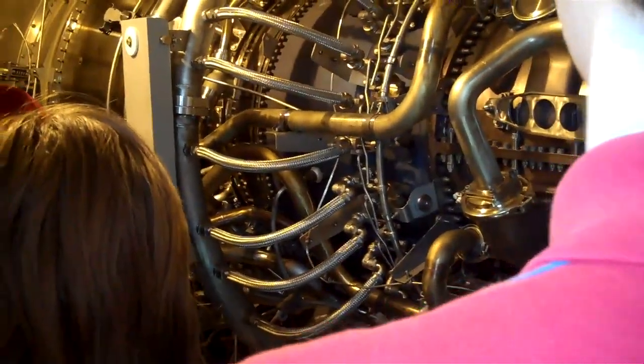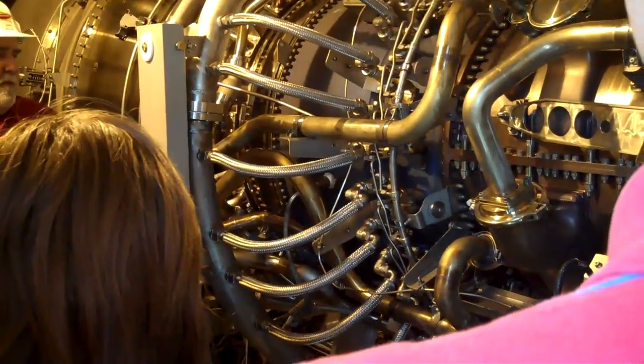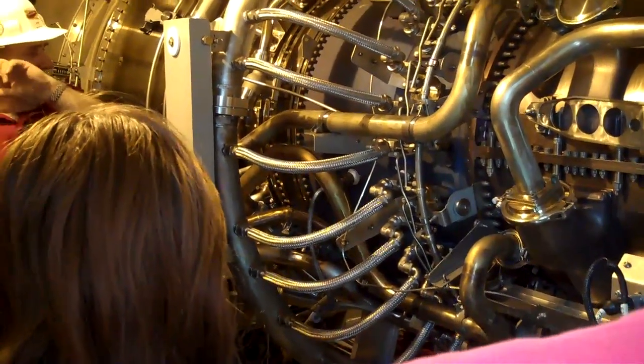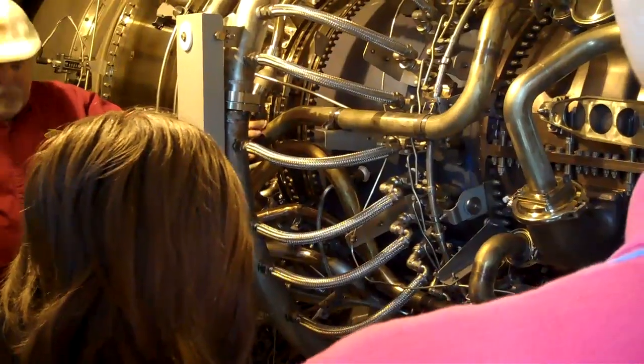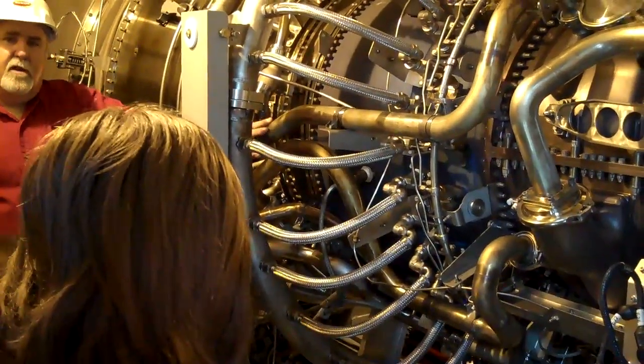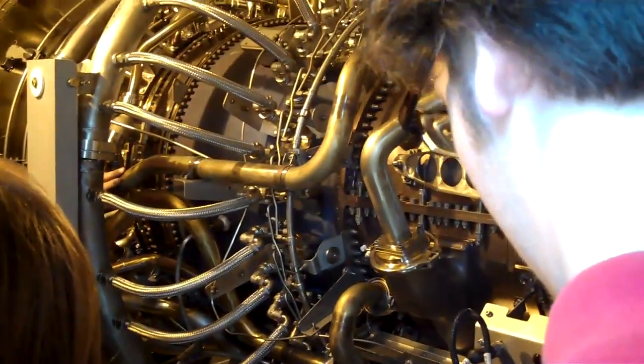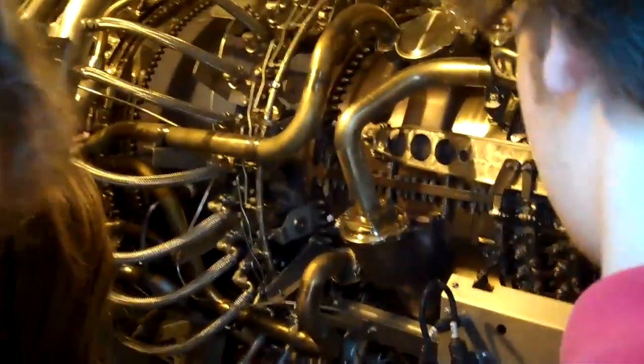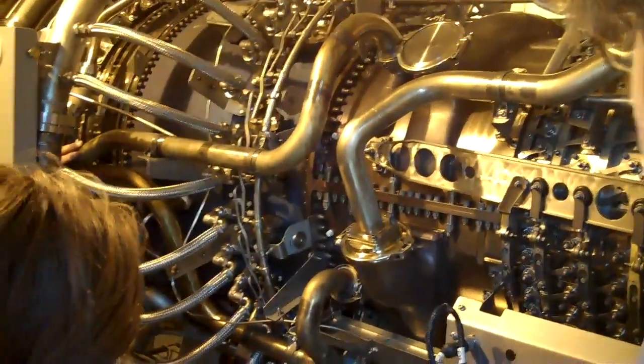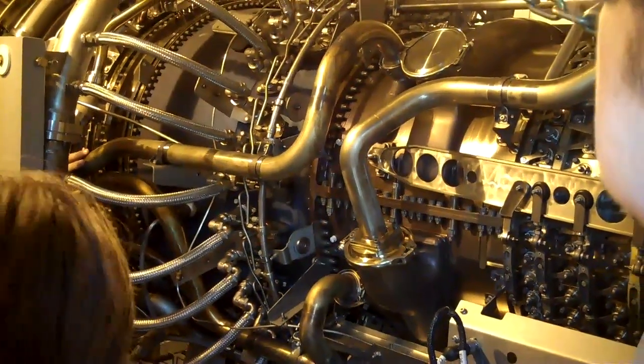The combined cycle type of unit does it a different way. It does the same principle but without injected water. The other thing is that these units have what they call SPRINT, where you can inject water into the compressor. If the temperature is not too hot, that'll make up the difference in that dense air so you don't have to run the air conditioning. So that's water injection.